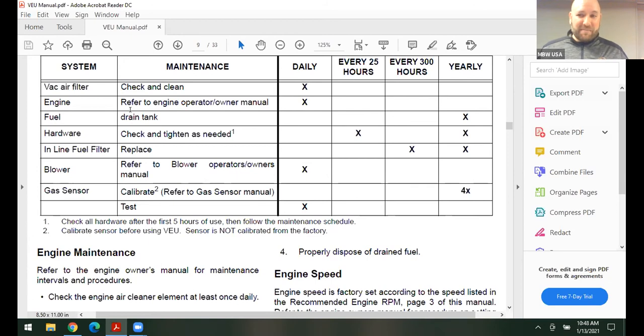We don't think about it, but this unit is vibrating and shaking, so make sure everything is tight. Check that yearly, if not every 25 hours. Also make sure your fuel filter's clean. I've seen utilities that bought spare parts kits but never swapped out the filter, and it's gotten gummed up, preventing fuel flow. So check that every 300 hours, if not yearly.